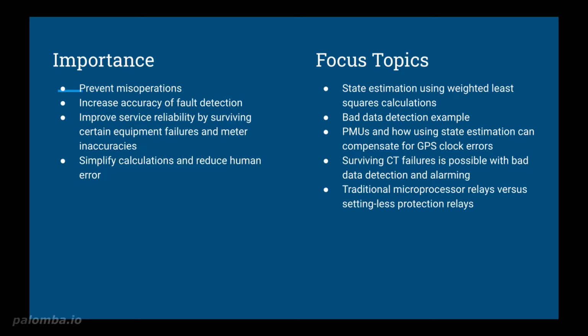The first area identified is the possibility of increased prevention of protective relay misoperations. This would improve both the reliability and selectivity aspects. Secondly, we have recognized the possibility of increasing the accuracy of fault detection. This would improve, again, both reliability and selectivity. We've also acknowledged the potential to improve reliability of the system by surviving certain equipment failures, mainly like instrument transformers and other sensing devices. And finally, we have also identified the prospects of simplifying the engineering calculations involved, which would tend to reduce the associated human error.